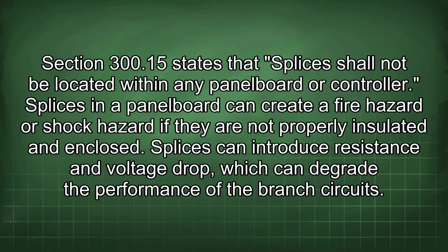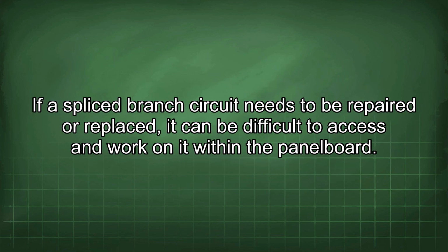Splices in a panel board can create a fire hazard or shock hazard if they are not properly insulated and enclosed. Splices can introduce resistance and voltage drop, which can degrade the performance of the branch circuits. If a spliced branch circuit needs to be repaired or replaced, it can be difficult to access and work on it within the panel board.